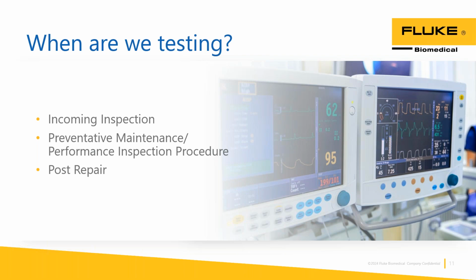And then post repair. Let's say you're taking apart the patient monitor and you make a quick repair, it's always important to test that device after the repair is completed. Let's say you're swapping out an NIBP motor. Because you've opened up that case, it's a good idea to check the other parameters also while doing your post-repair checks, because it's possible you bumped a cable or something was close to going out, and now it has gone out. Make sure you do a check after that.